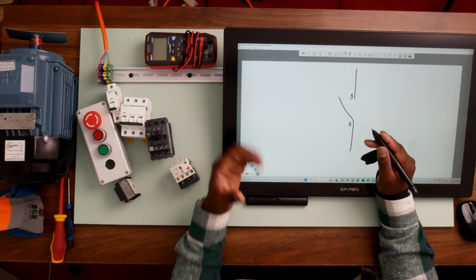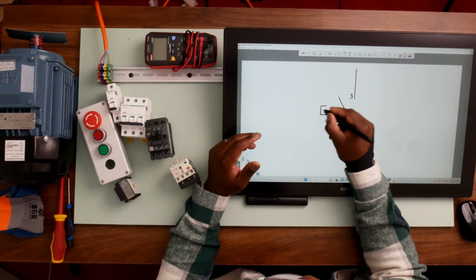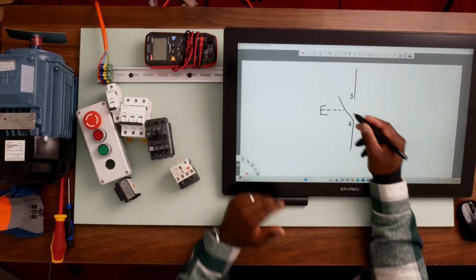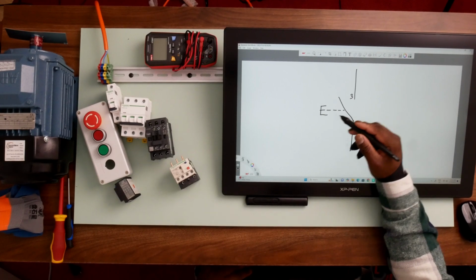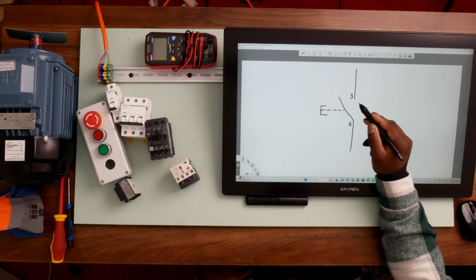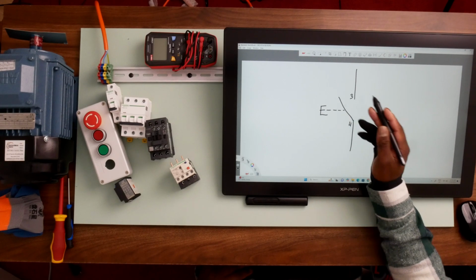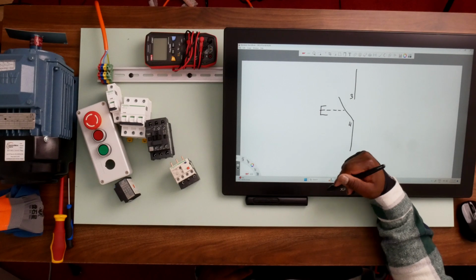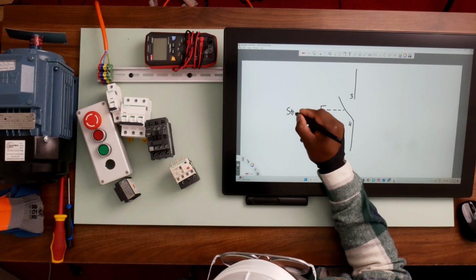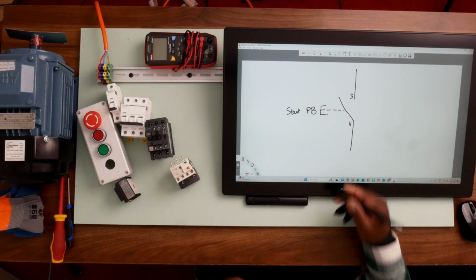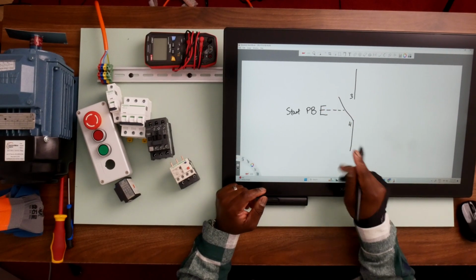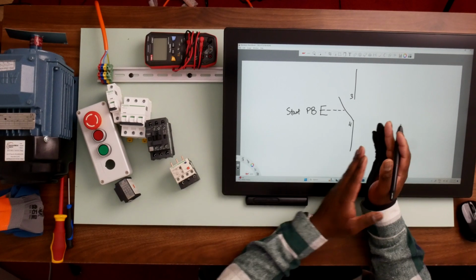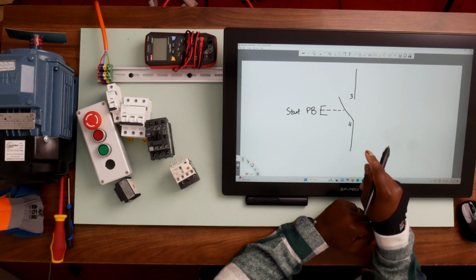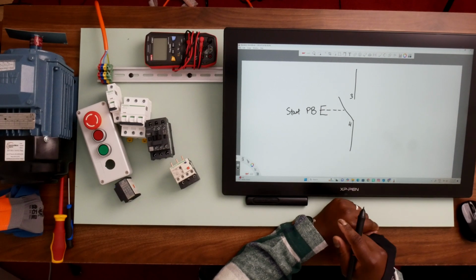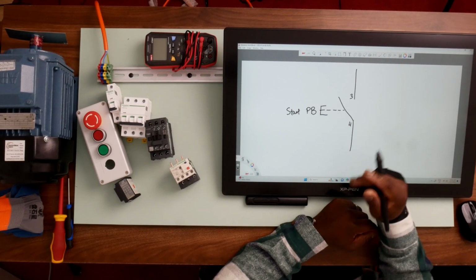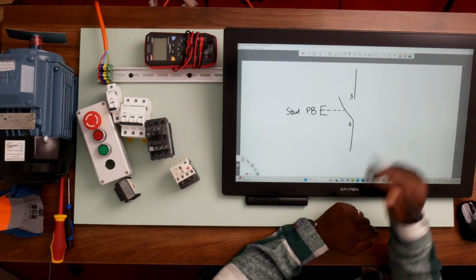Now we need something that tells us that it's a push button. So we draw our general symbol for a push button, and the dotted line linked to our contact here. So this tells us that this push button is mechanically linked to this contact. So this push button is the one that is operating this contact. So this is your start push button, and it's a momentary contact, which means if we press it, it only remains engaged, or in the closed position, as long as we maintain our finger on that push button. But as soon as we release our finger from the push button, this contact goes back to its default state, which is the normally open position.